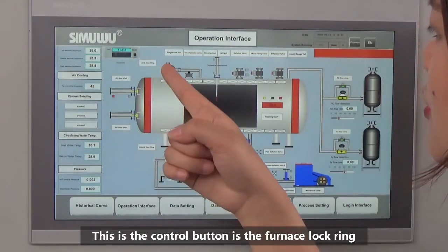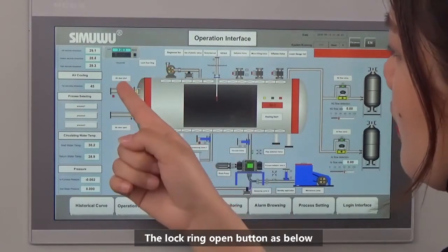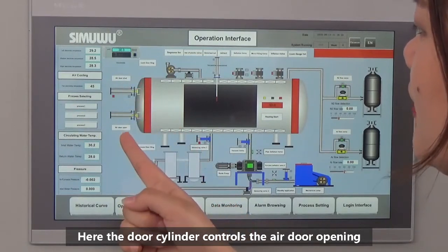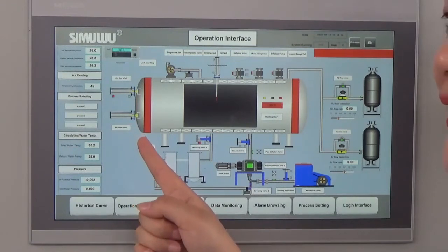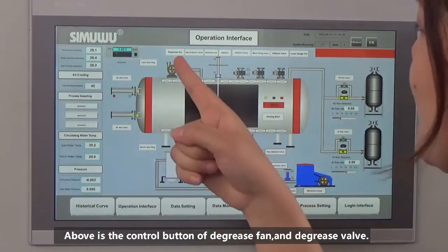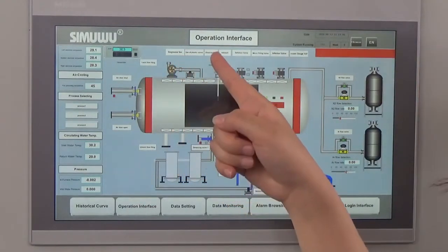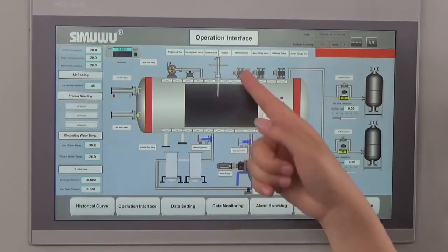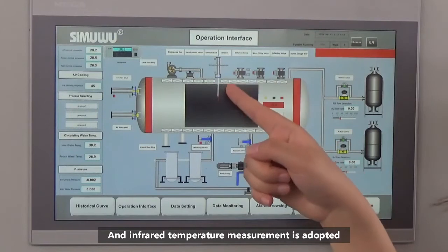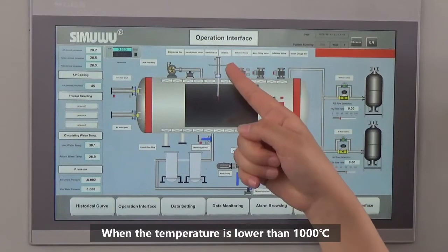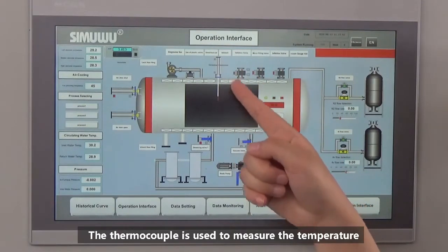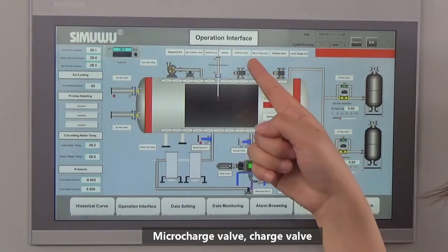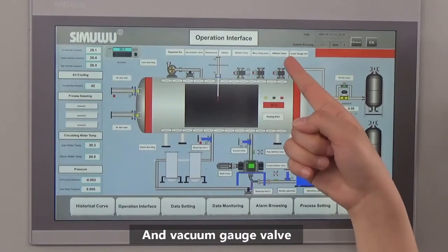This control button is the furnace lock ring — click here to lock it, and the lock ring open button is below. Here is the door cylinder control for opening the air door, and the other door cylinder control is for closing it. Above are the control buttons for the degassing fan and degassing valve. Thermocouple out and thermocouple in: when the temperature is more than 1,000 degrees centigrade, the thermocouple needs to be removed and infrared temperature measurement is used instead. When the temperature is lower than 1,000 degrees centigrade, the thermocouple is used to measure temperature. This position has control buttons for the deflation valve, micro charge valve, charge valve, and vacuum gauge valve.